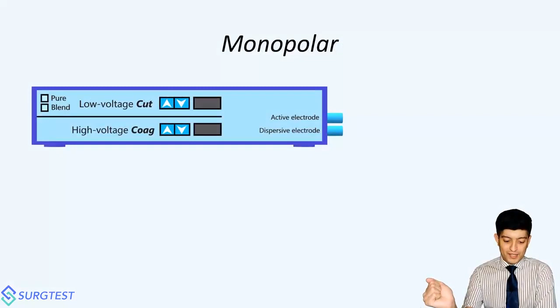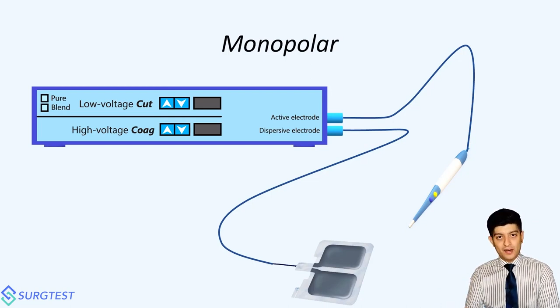So let's start talking about monopolar current. We all have 2 wire attachments on the ESUs. One is for the cautery pencil and the other is for the grounding pad or the dispersive electrode, which is present on the patient. At the outset, let me just say that calling this a grounding pad is not correct, because a grounding pad would mean the pad directly connects into the ground. This used to be a feature of very old electrosurgical units early on, like within the first 20-25 years. But note that there was no control over how much energy would actually be flowing into the ground.